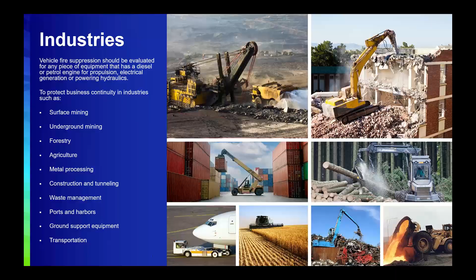As we discussed, deciding what to protect and what not to protect is really determined through a fire risk assessment, or FRA, also known as a hazard analysis, and this is the key first step to understand whether a piece of equipment would benefit from a fire detection and suppression system. The FRA reviews the general vehicle layout, the occupants' interaction with the vehicle, where ignition sources exist, what the potential sources of fuel are, how fire can propagate throughout the equipment, how big a potential fire could be, often dictated by the available source of fuel, and the ability for an operator to safely egress.